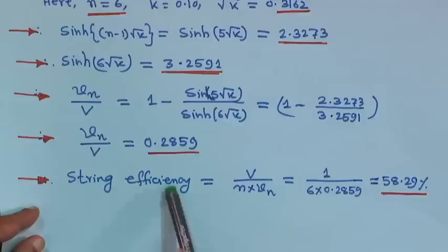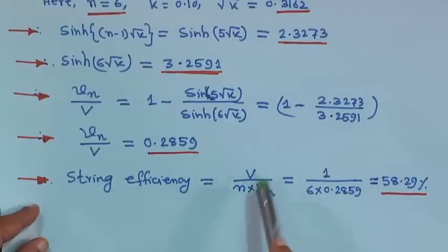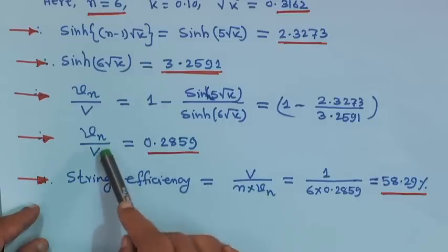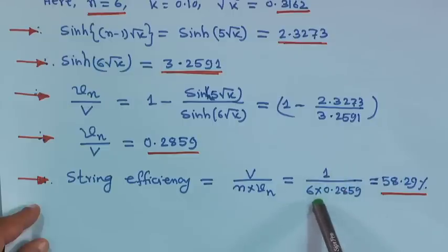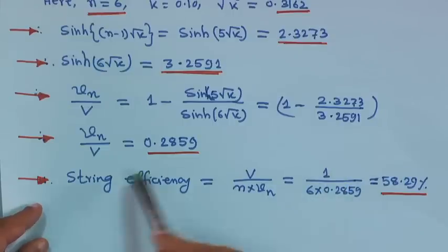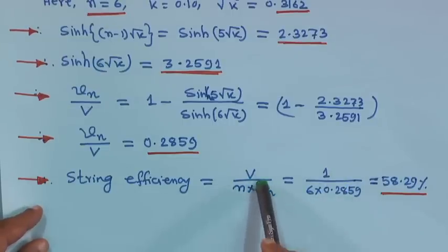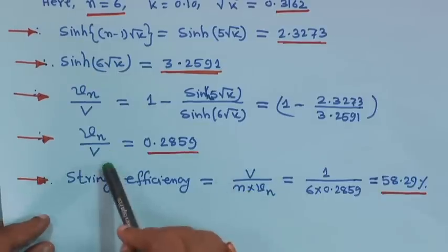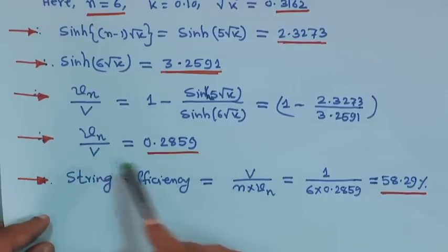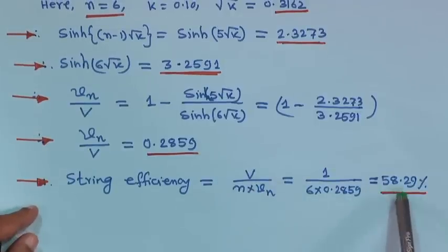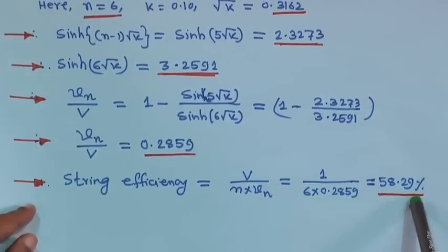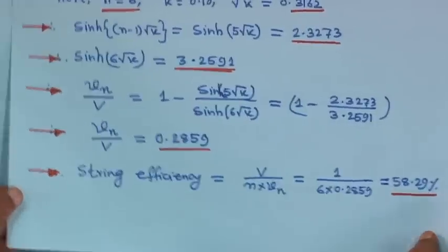V_n/V is 0.2859. Therefore, string efficiency equals capital V divided by n times small V_n. Since V_n/V is 0.2859, it is 1 divided by (6 × 0.2859), which comes to roughly 58.29 percent. That is the string efficiency.